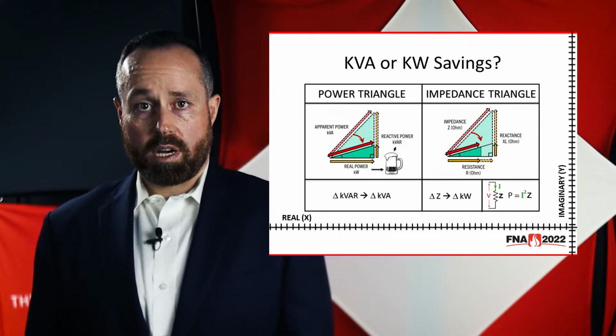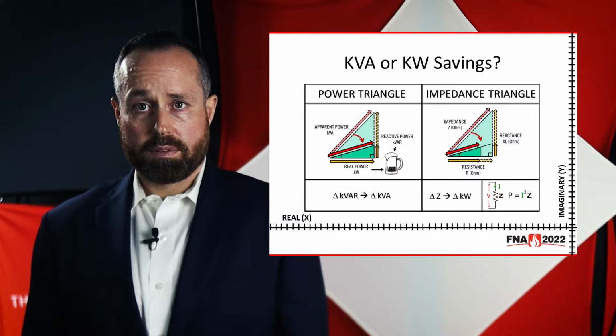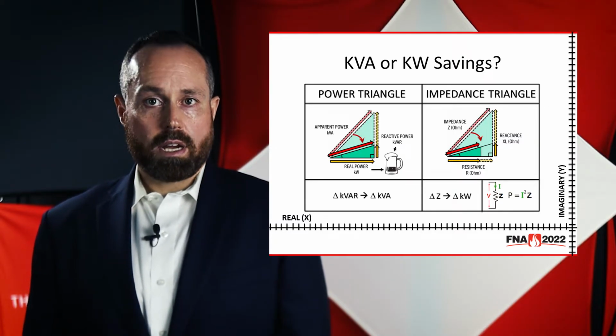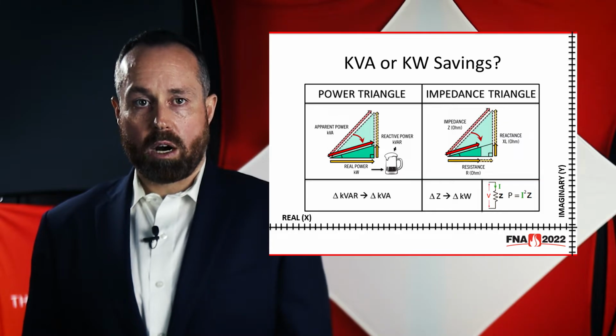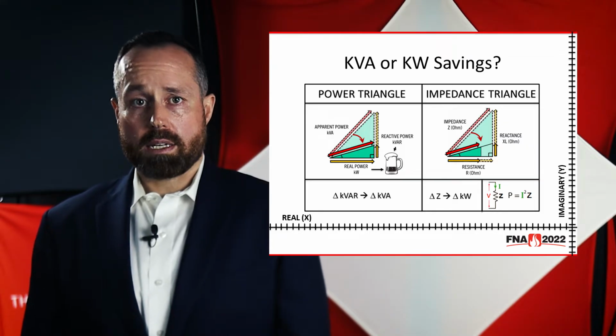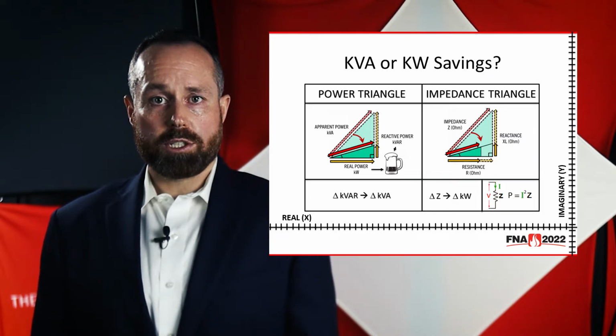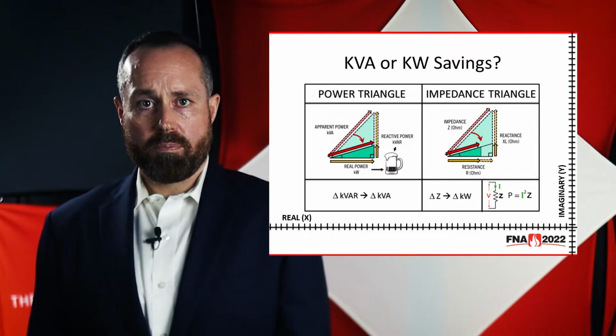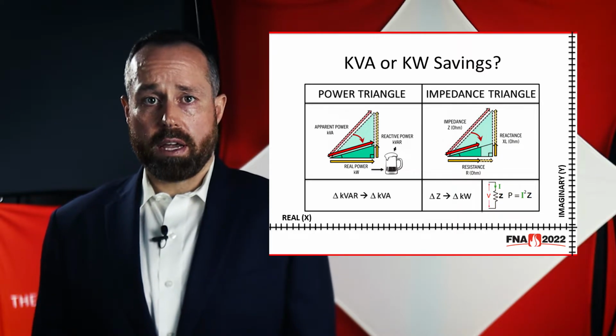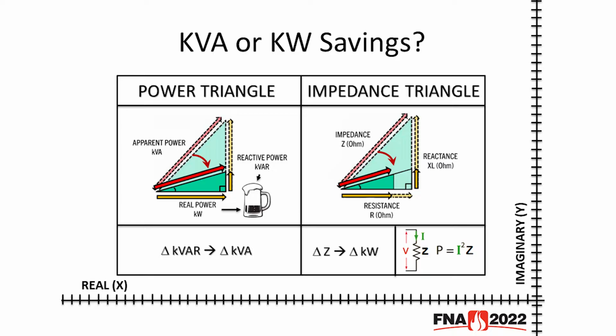kVA is commonly described with the power triangle shown on the left. On the x-axis, there's kW, which is the real power or the power that's doing work. And on the y-axis, there's kVAR, which is the imaginary reactive or wasted power. These are 90 degrees out of phase and are vectorially added to calculate the kVA. The action shown in the triangle demonstrates the changes we discussed in case 1. A reduction in kVAR with the same kW results in lower kVA. So what about kW savings?